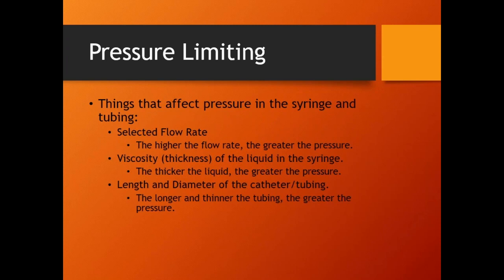Yeah, next. Things that affect pressure limit: selected flow rate, and the viscosity of the fluid, I didn't get to bring up that one. The contrast syringes. You notice there are 2 syringes here. One's for contrast, one's for saline. Most of your CT injectors these days are going to have 2 syringes, one for contrast, one for saline. If your hospital utilizes a 16 slice or better CT system, which I can't imagine any of them don't now, and they use post-processing to create a lot of the images they need, it's not just a CT injection, it's a CTA injection, CT angiography. To get the angiography part, to fully maximize it, they need the saline, for several different things, which we won't go into with this listing. So yeah, CT syringe and angiographic syringe.